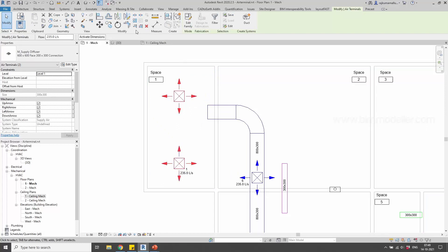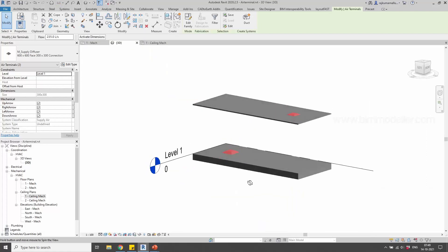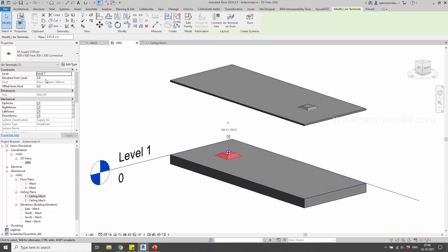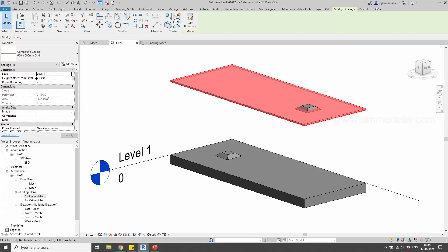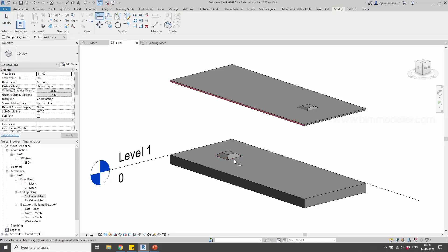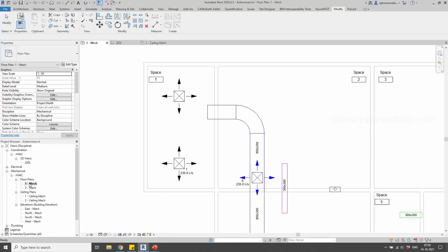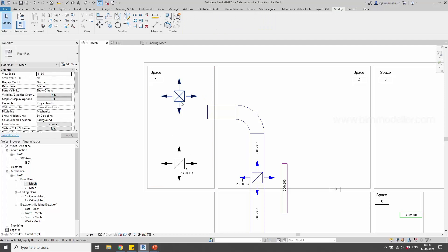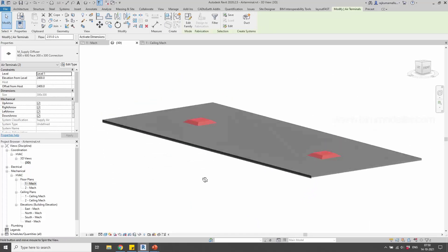If I select both of them and click the section box option (BX), you'll see the last one placed is on the floor, because the elevation from level is 0. Most of us make this mistake. The ceiling height is 2400, so we have to place them at 2400. You can use the Align command, or simply select them, go to the floor plan, and change their elevation value to 2400. Now in 3D, both of them are placed in the ceiling.